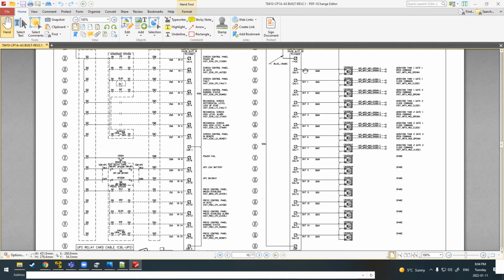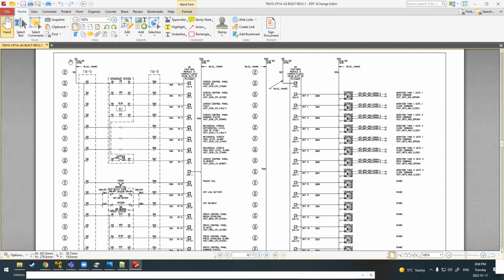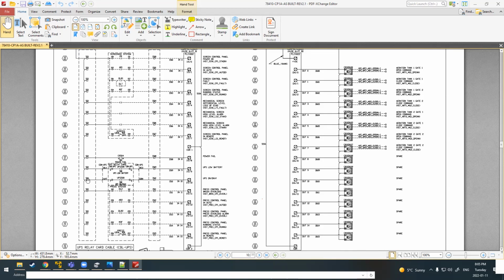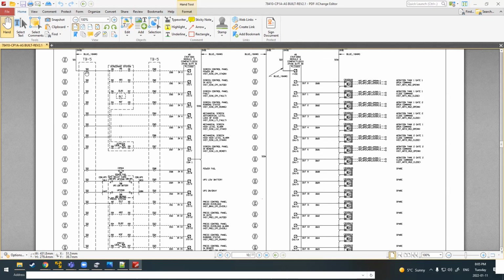And then these are your outputs. So you'll see here, it's showing, oh, I guess I didn't even touch this earlier. At the top of the IO cards here, it's showing 24 volts coming down to one terminal block, and it's being jumped all the way down. So all of these terminal blocks in the panel will be commented up, and then individually each input has their own terminal block on the other side. TB5, this will line up with a certain section of the panel. 24 volts passes through this device in the field. When 24 volts comes to this input, that input will turn on.